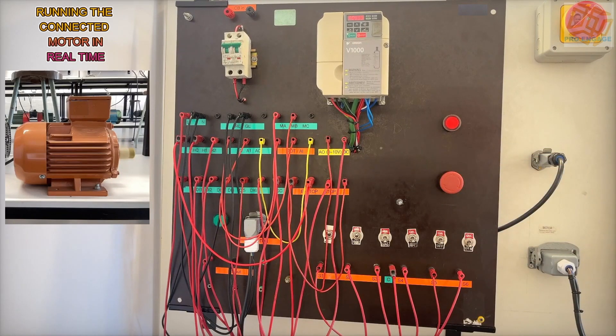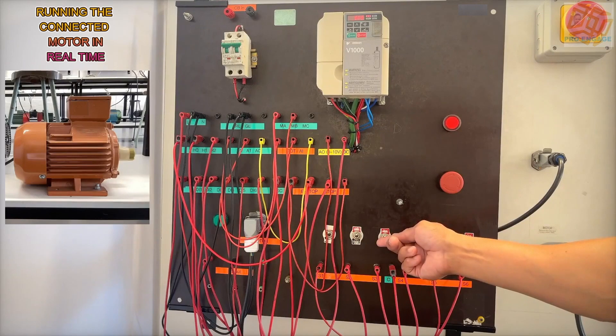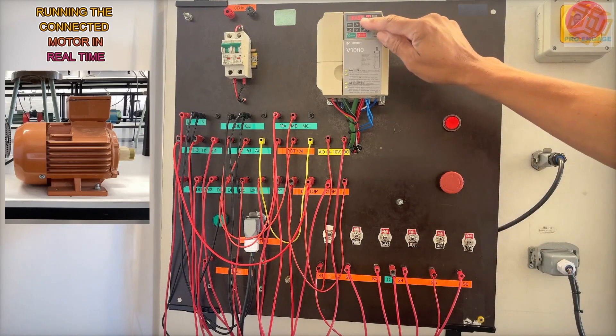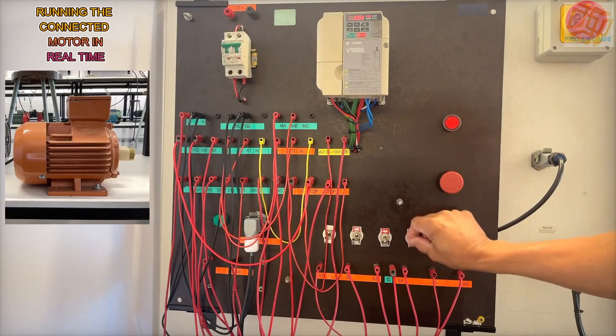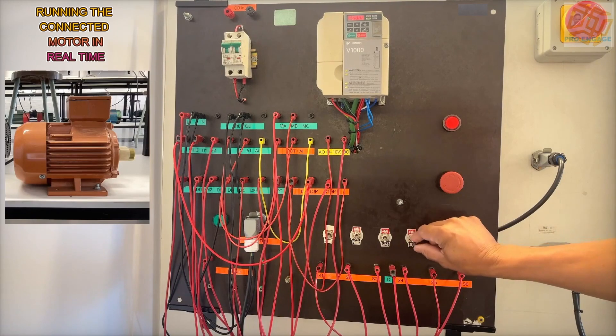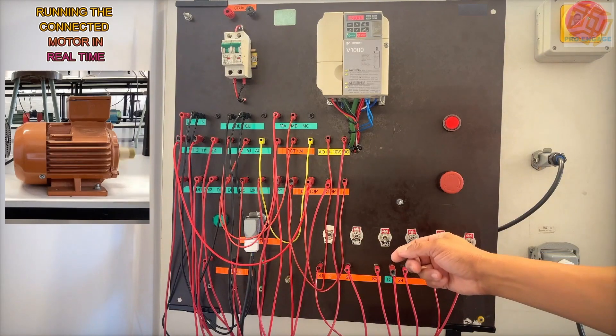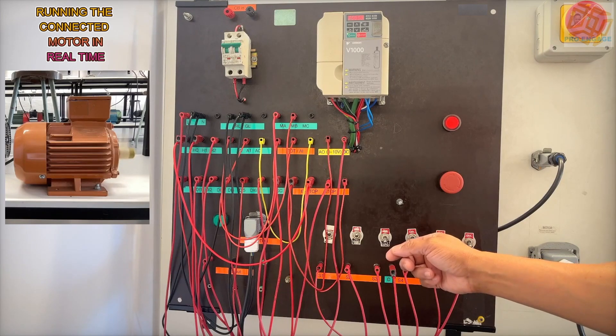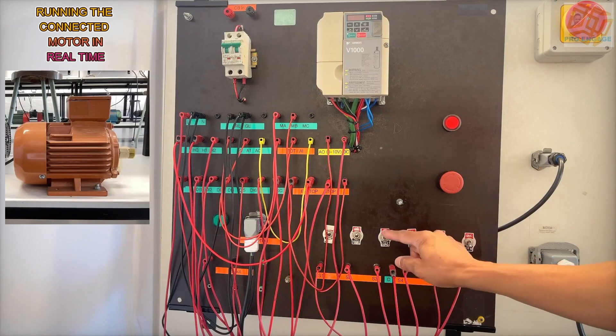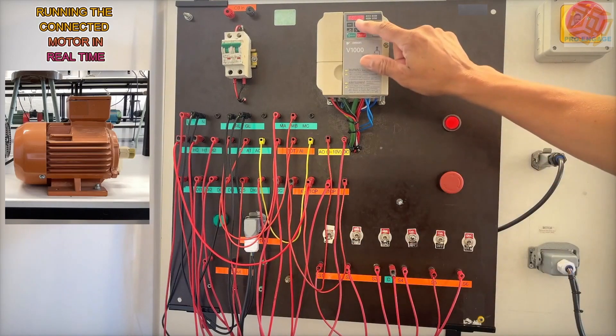I'm going to do some more other actions with this. The third switch there is set as a fault so you will see a fault signal on the screen. The fourth one is to reset the fault. I have to obviously push all the buttons down in order for the fault to be reset. You can see on top there it will go back to 50 hertz. If that's not on the screen the fault is not reset. Let's do this again. Put the fault reset, put everything down, then flip this switch once or twice and it will reset.